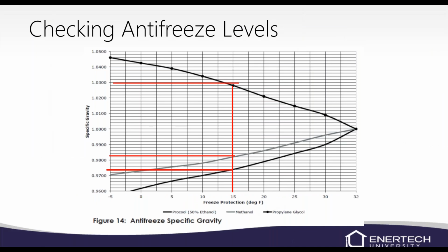Measuring antifreeze levels, we kind of discussed that. Above the 1.0, 1.0 is straight water. So above the 1 would be propylene glycol, and below the 1 would be methanol or ethanol, alcohol-based. And we're trying to get normally about 15-degree freeze protection. We normally will design a loop for 30-degree lowest water temperatures on design days. But as you know, we have non-design days where we're going to drop that loop field. So we give it a 15-degree window from whatever our loop field is designed at for protection. So we go down to 15-degree freeze protection.